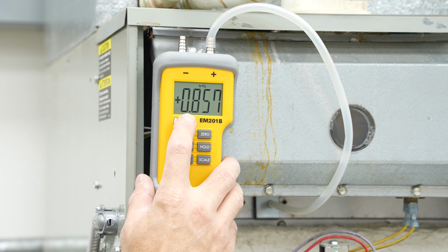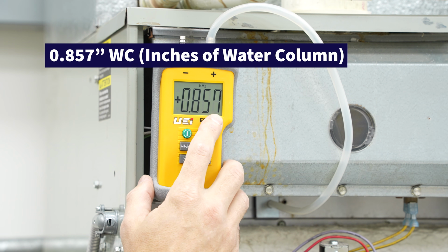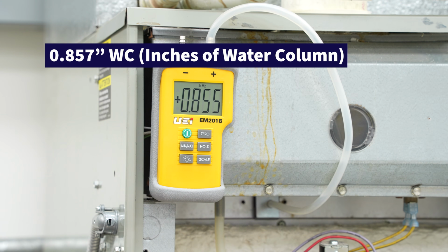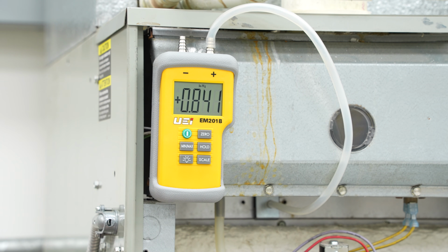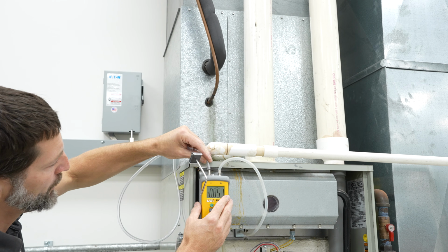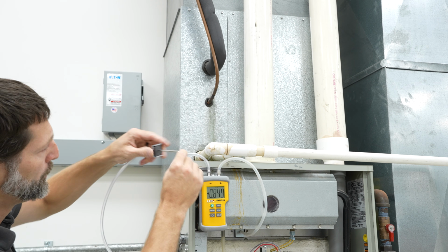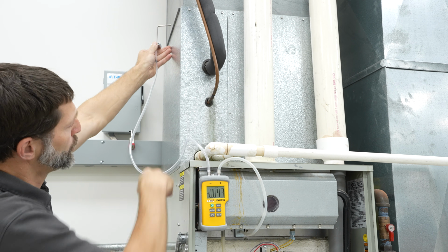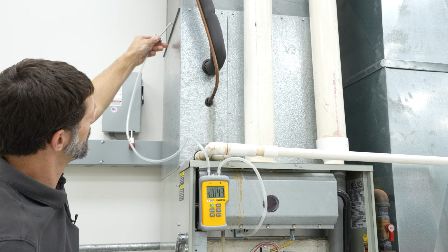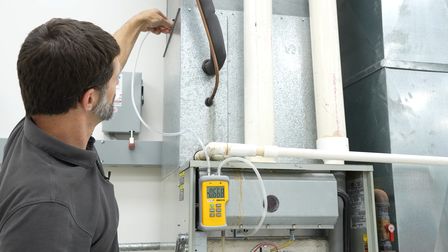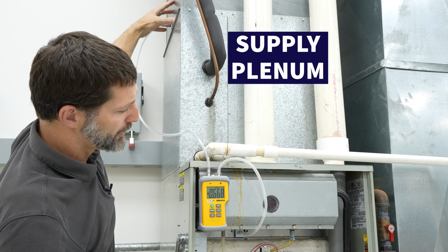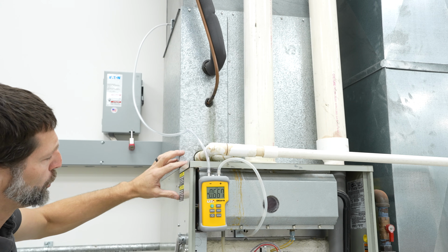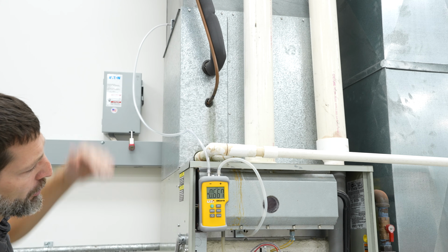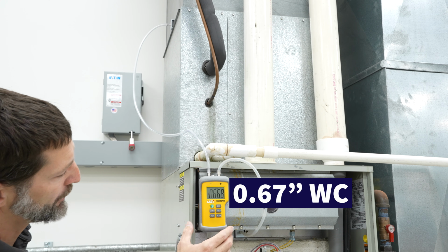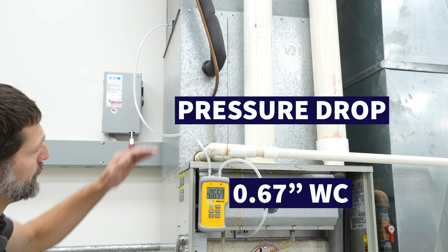So right now you see we're measuring a static pressure of 0.857, so that's a very high static pressure. That is measuring everything that is downstream of the blower motor as positive pressure. Then we're going to add our second pressure tip on this side of the coil. So we need to drill a hole in the supply plenum in order to put this tip.